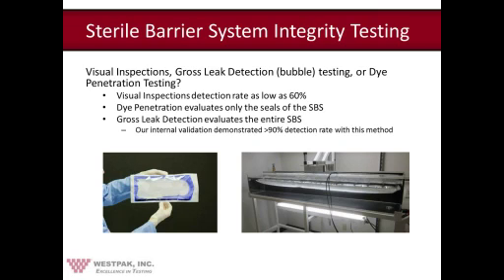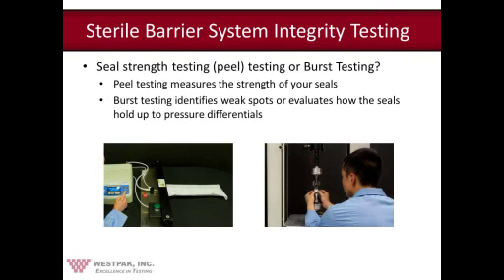Gross leak detection or bubble testing would be more appropriate, I'd say. It tests the entire package. It tests the seals and it tests the surface. Our internal validation with ASTM F2096 here at Westpak showed greater than 90% detection rate, so this is the testing that we suggest for this. As far as demonstrating adequate seal strength for your pouch or tray, a question sometimes we get asked is, are peel testing and burst testing interchangeable?